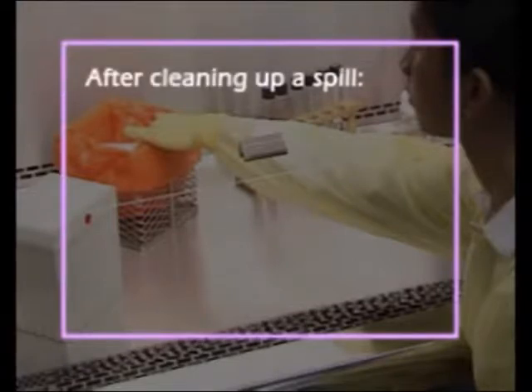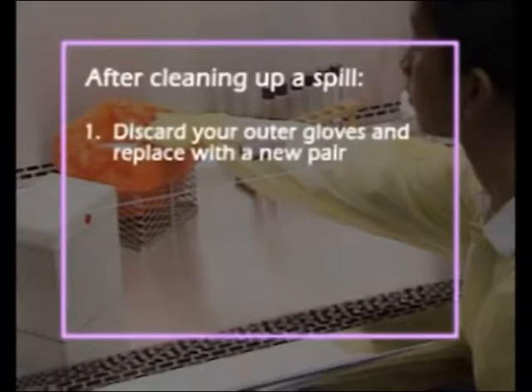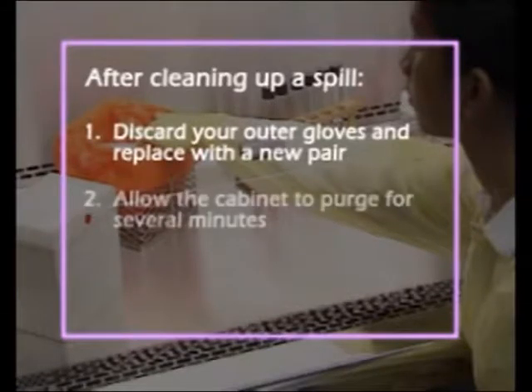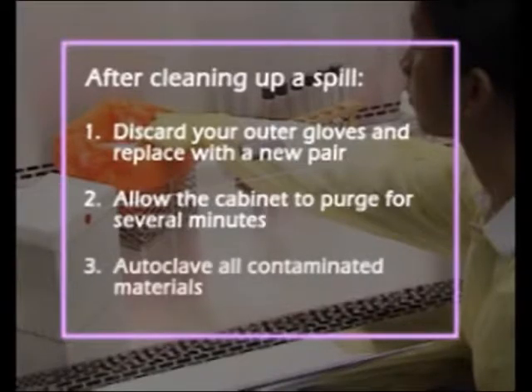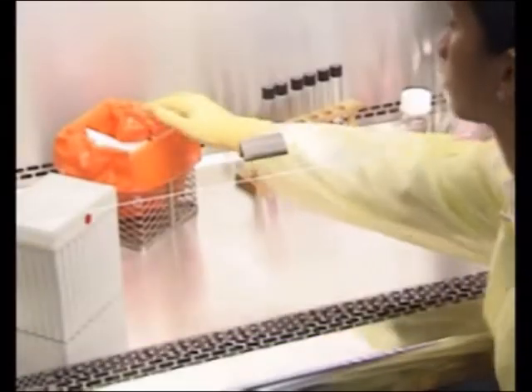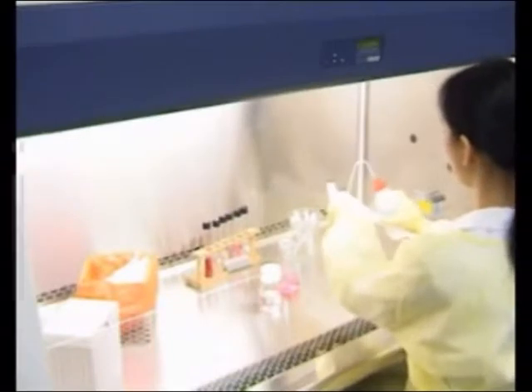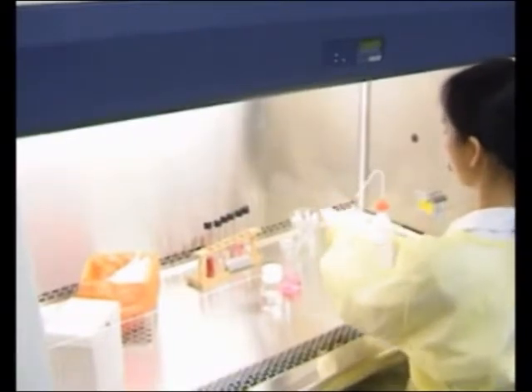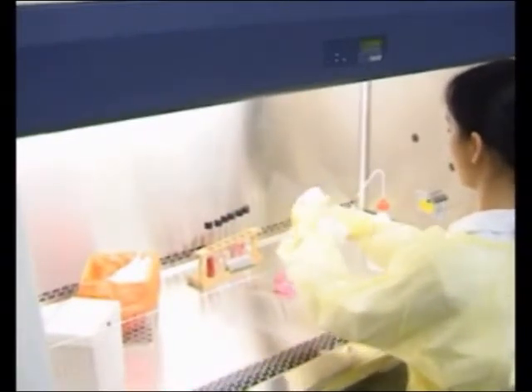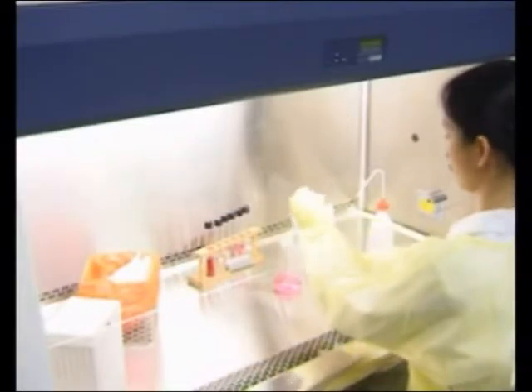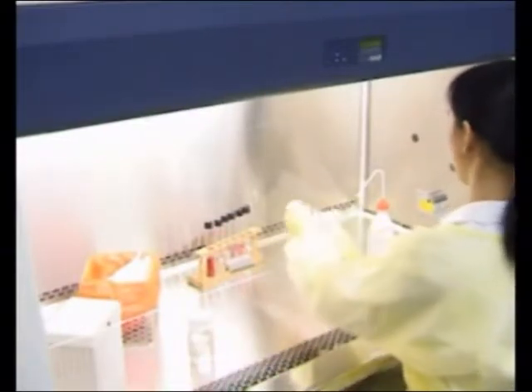After cleaning up a spill, discard your gloves and replace them with a new pair. Allow the cabinet blower to run, purging the work zone for several minutes. And be sure to autoclave all contaminated materials. After completing your work, run the biosafety cabinet for 2 to 3 minutes without activity to purge the air. Disinfect the outside surfaces of all items to be removed from the biosafety cabinet.